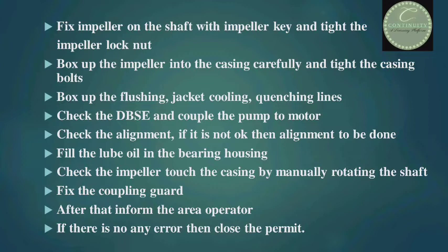Box up the impeller back plate. Fix the impeller on the shaft with the impeller key and tighten the impeller lock nut. Box up the impeller into the casing carefully and tighten the casing bolts. Box up the flushing jacket, cooling, and quenching lines. Check the DBSE and couple the pump to the motor. Check the alignment — if not okay, perform alignment. Fill lube oil in the bearing housing. Check that the impeller does not touch the casing by manually rotating the shaft. Fix the coupling guard and inform the area operator. If there is no error, close the permit.